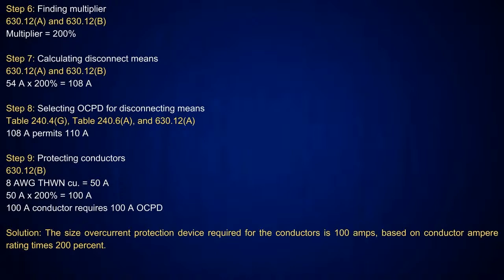And then I'm going to look at 630.12a, and you look at 12b, it all ties in the same there. It's going to tell you take it at 200%. So I take 54 amps at 200%, gives me 108 amps. And I can look at this 2 ways to provide this protection. Now, I can say, all right, I'm going to protect the conductor at 110 amps, but I'm going to see if I could just do 100 amps. Okay, which I can already tell you it is, because if I take 50 amps at 200%, what does it give me? 100 amps. See that?